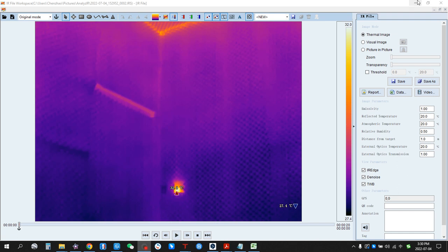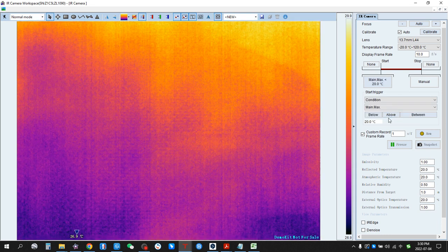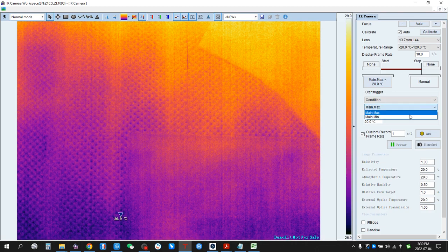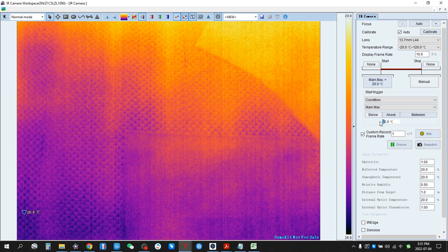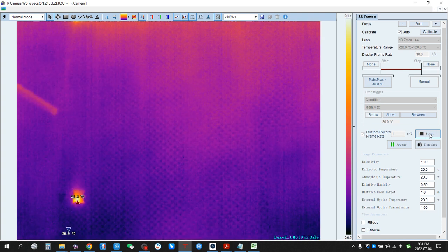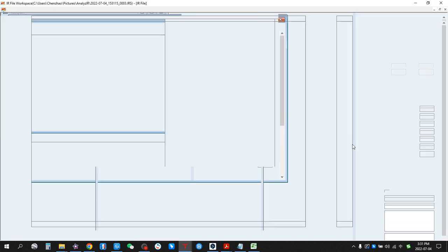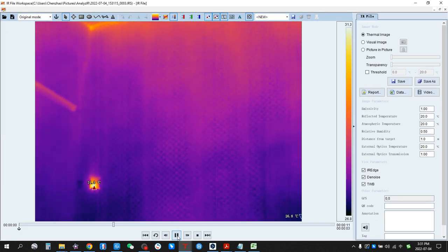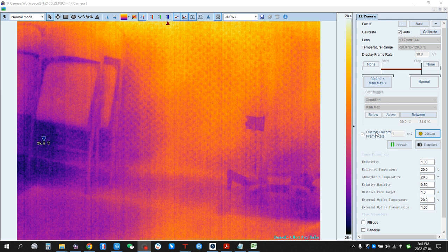We can also use a Condition trigger. For example, we can set maximum temperature as the trigger for recording. We can set it to about 30 degrees Celsius, then arm it, scan, and find a spot of 31 degrees. So now it's recording automatically. Stop — the video is recorded. We can play it. We can also set an upper limit and a lower limit of temperature for recording.